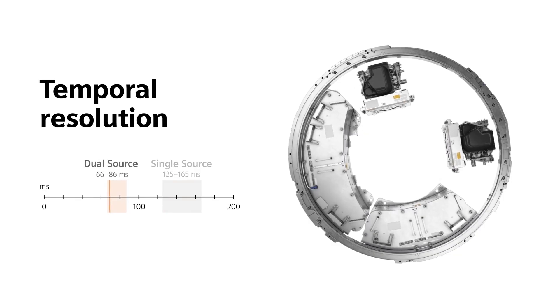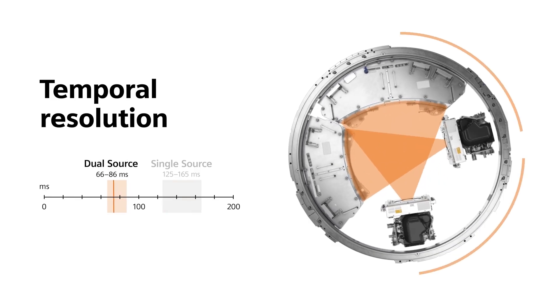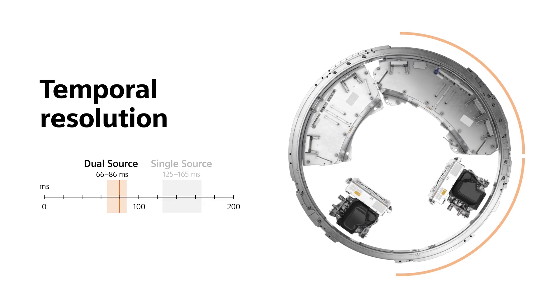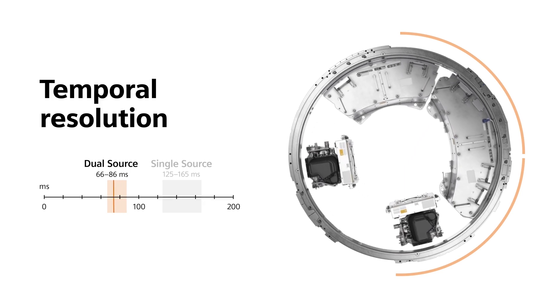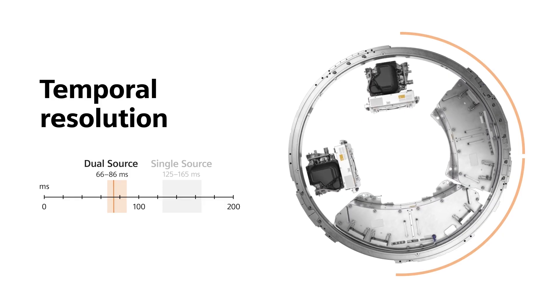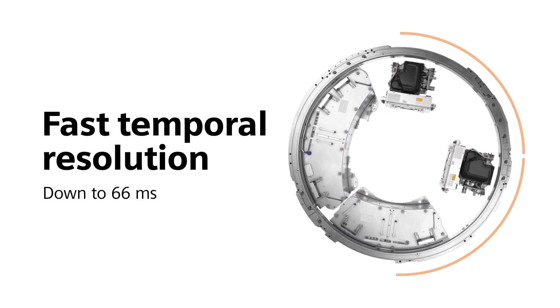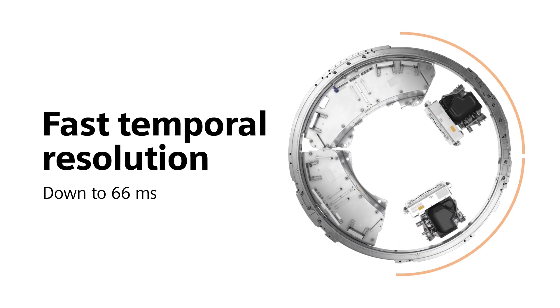It's a completely different story with dual-source CT, because the tubes can work together to help you speed up your scans. When you set each tube to perform only a quarter rotation, you still get a half rotation in total. This enables you to achieve fast temporal resolutions between 66 and 86 milliseconds, dependent on the system.